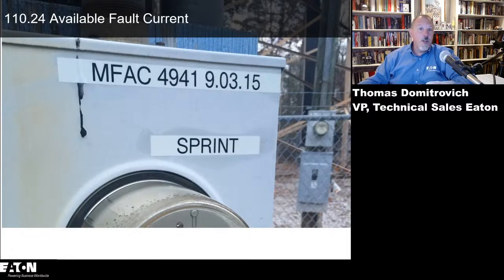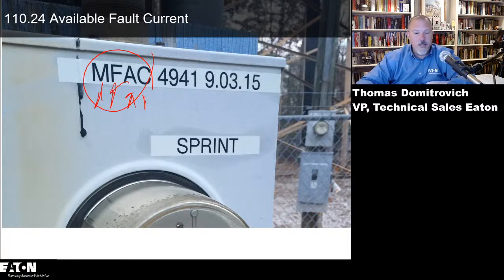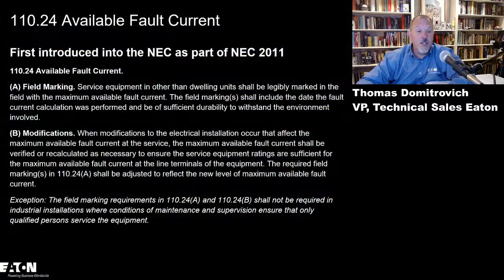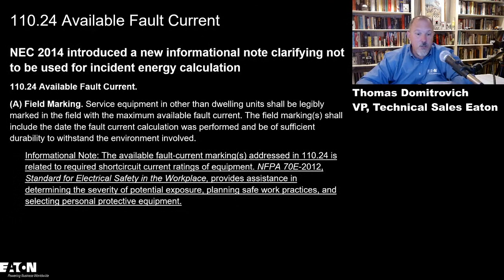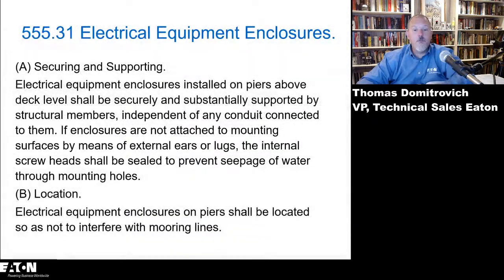So, and this is in the Marina area where we have this installation. So, you're going to have to put the marking of available fault current. So this is your maximum fault available current. I think that's the way Alabama does it. But that is telling you that you have 4,941 and the date that meets the National Electrical Code requirements. So you still have to follow the rules in 110.24 for marking of available fault currents in those locations.